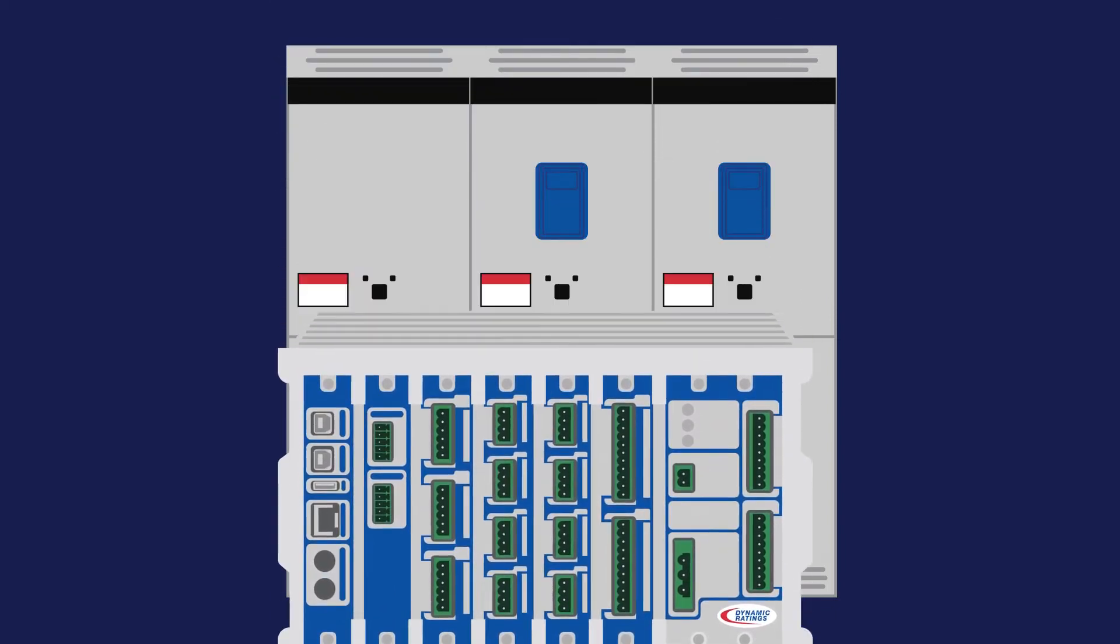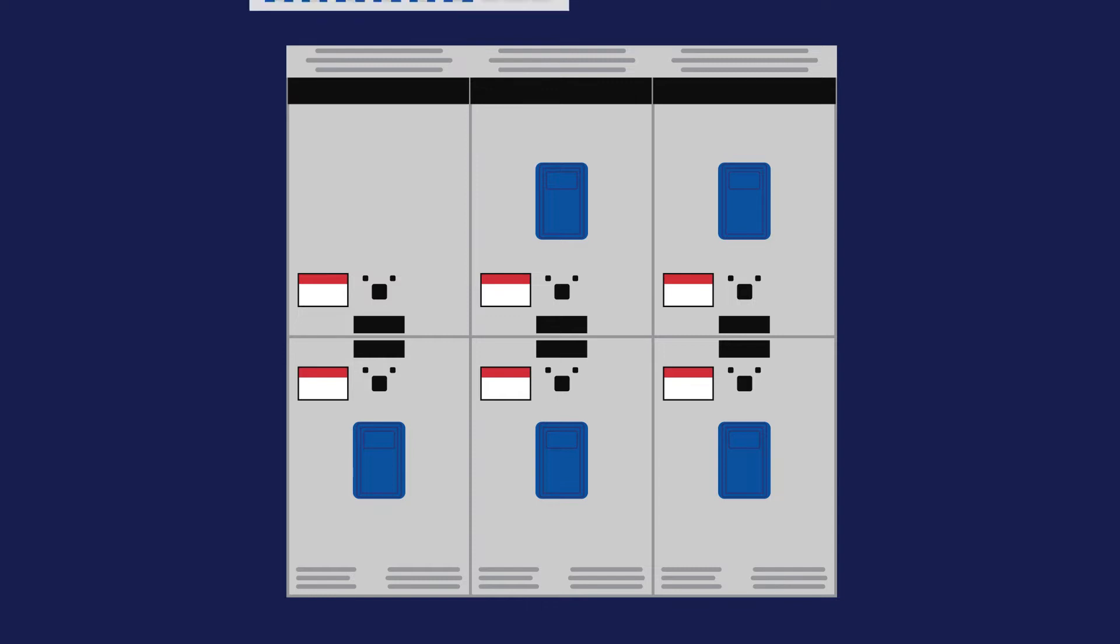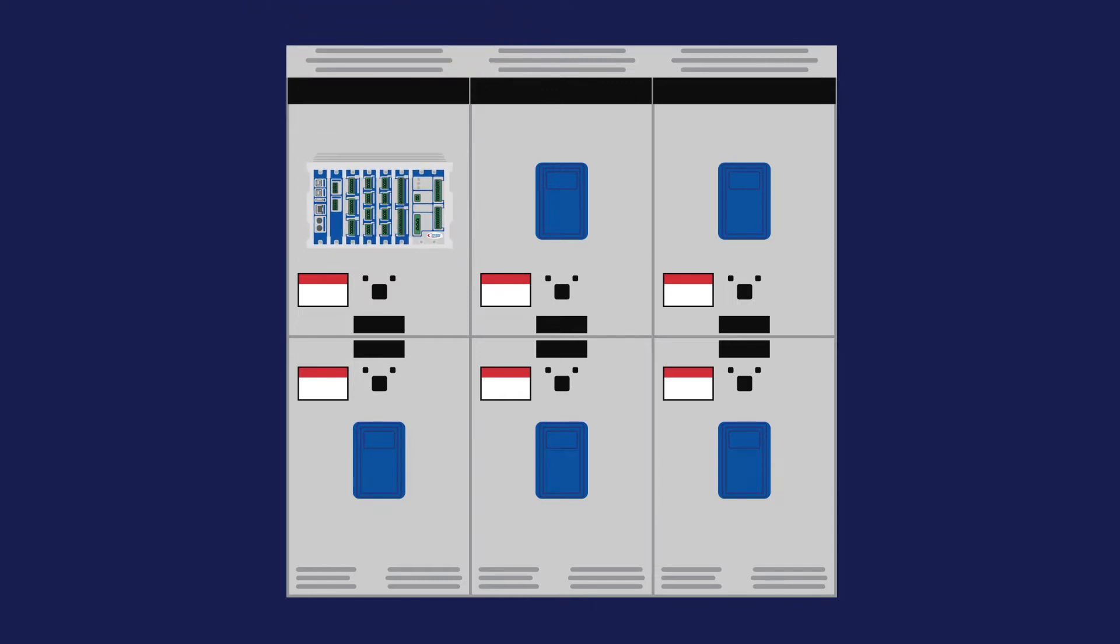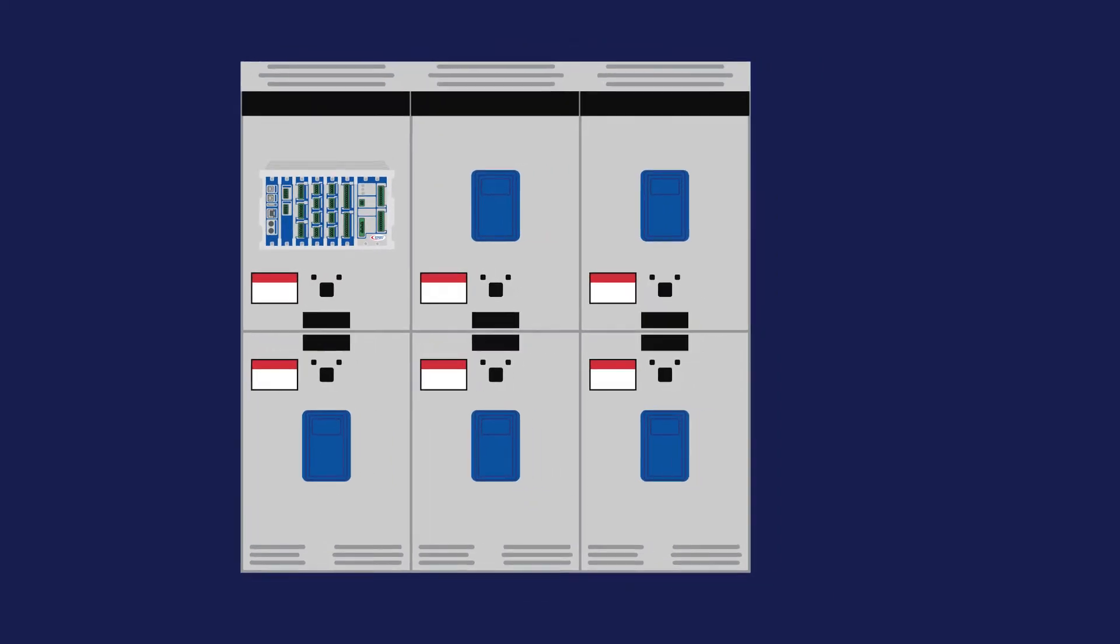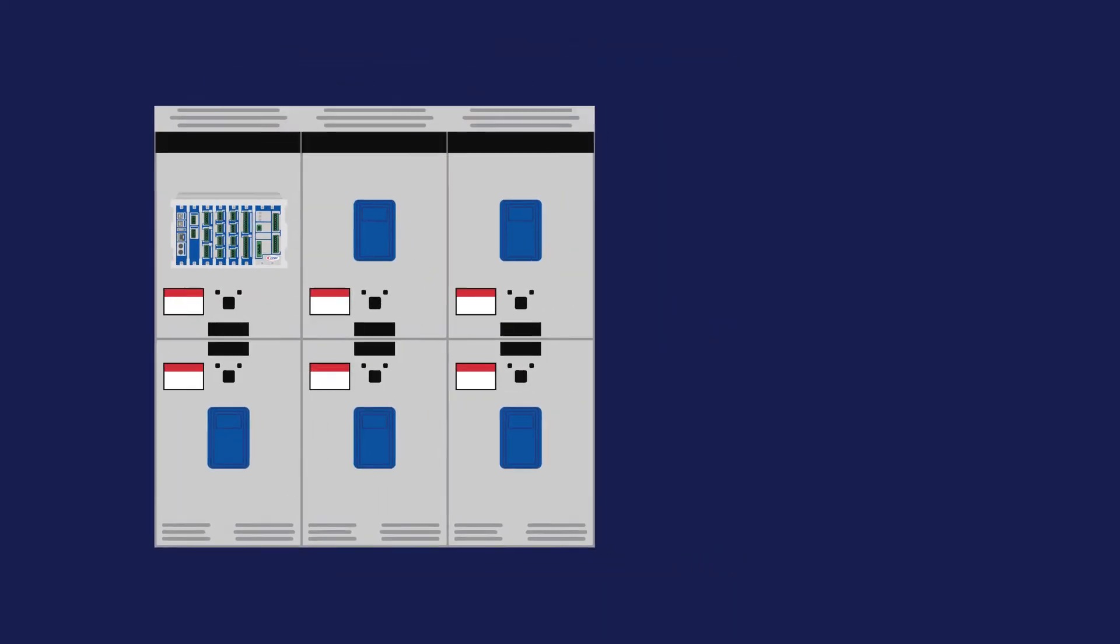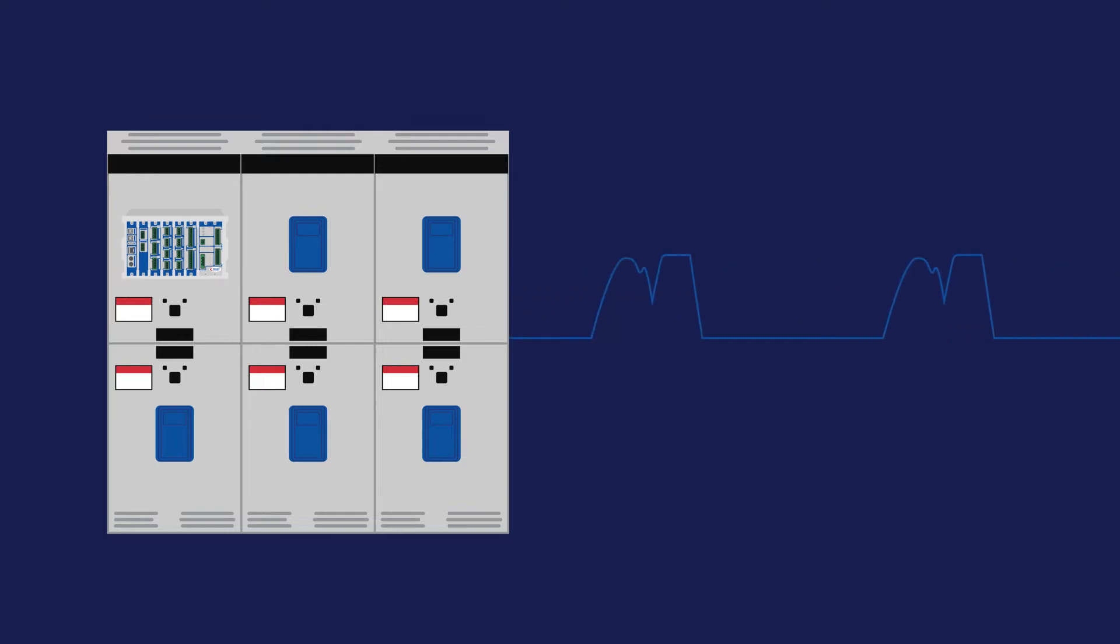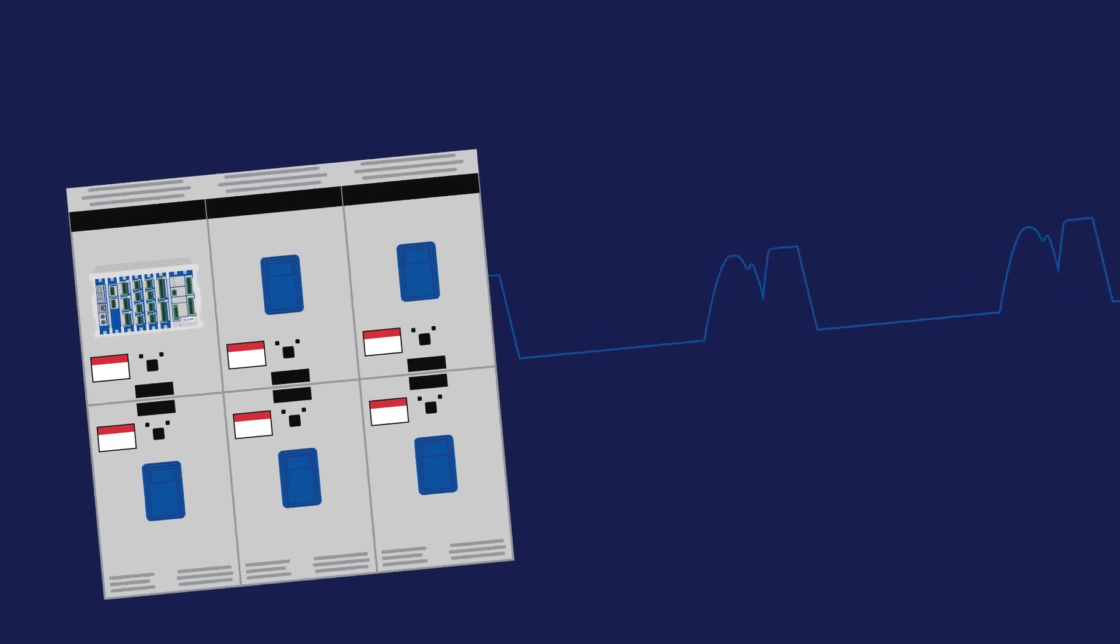Dynamic Ratings Switchgear Monitor captures small changes in switchgear performance, allowing problems to be detected well before failure occurs. Using Dynamic Ratings Smart Capture technology, the switchgear monitor can capture waveform signatures as they relate to the operation of the trip and close coils during breaker operations.